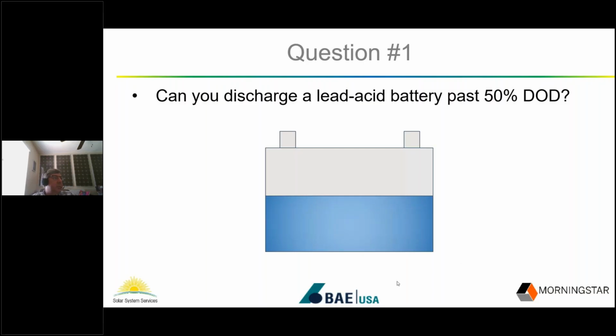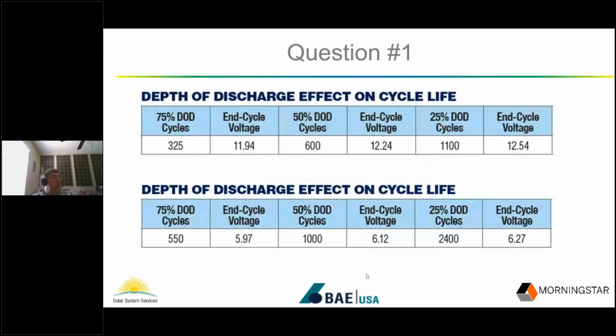As an example, here's a 12-volt AGM battery, and you can see you can only discharge it about 325 times at 75% DoD. That's not much—if you're cycling that every day, that's 1 year and the battery's done. There's another one from the same manufacturer, their 6-volt battery, which can cycle up to 550 times to 75% DoD. That's still not great if you're cycling it that deep every day, because that means only about 2 years or less on that battery.